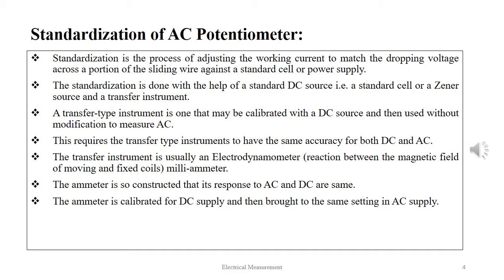This requires the transfer type instruments to have the same accuracy for both DC and AC. The transfer instrument is usually an electrodynamometer. The ammeter is so constructed that its response to AC and DC are same. The ammeter is calibrated for DC supply and then brought to the same setting in AC supply.